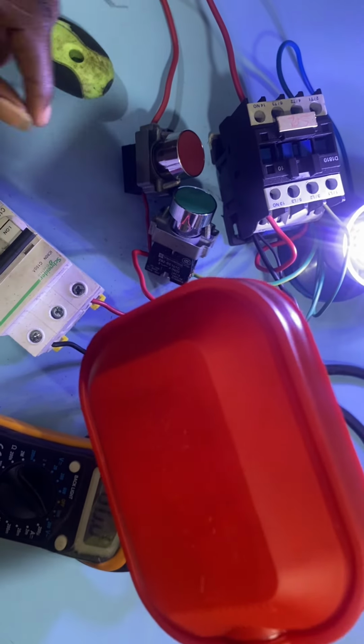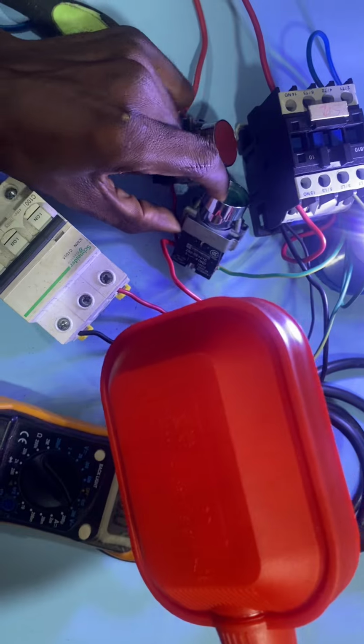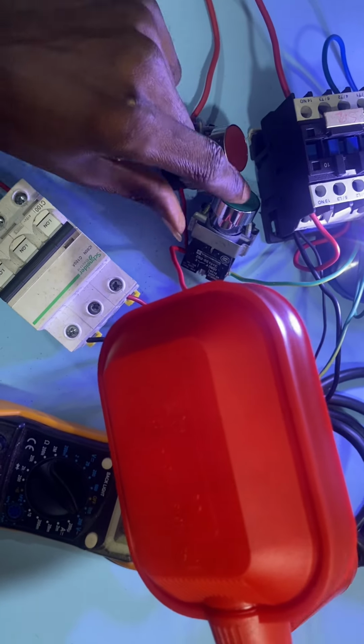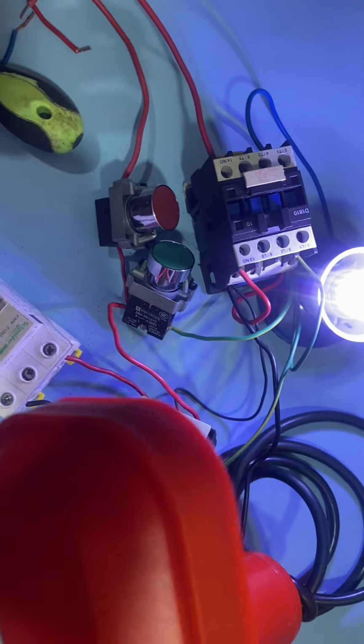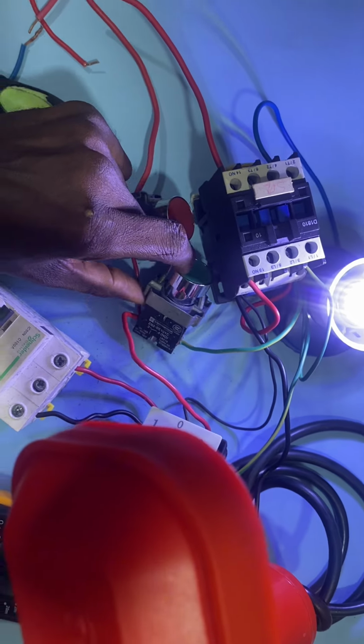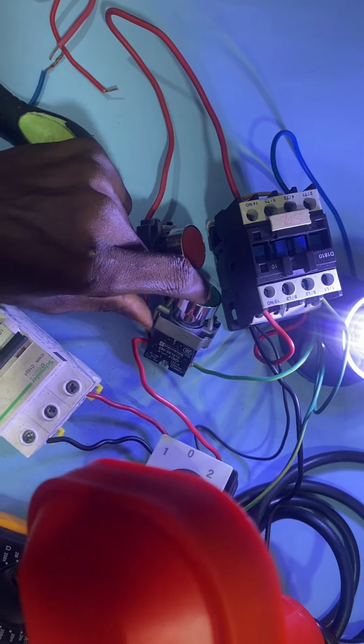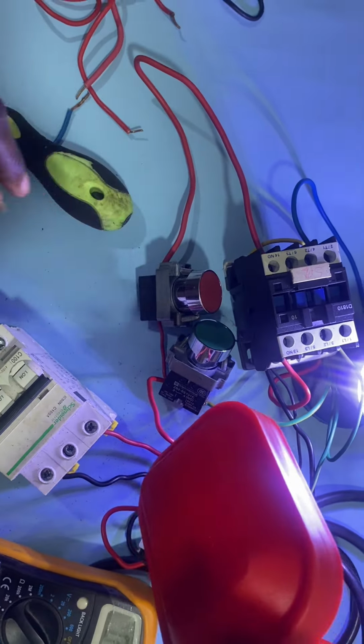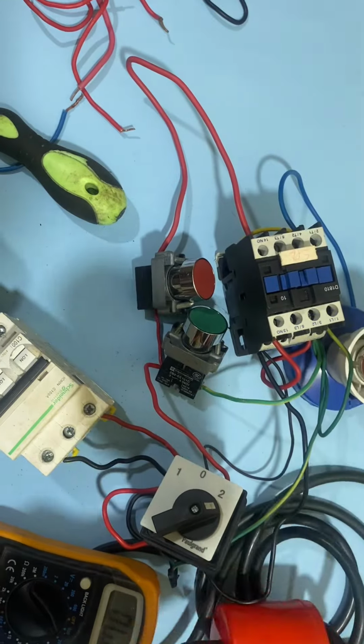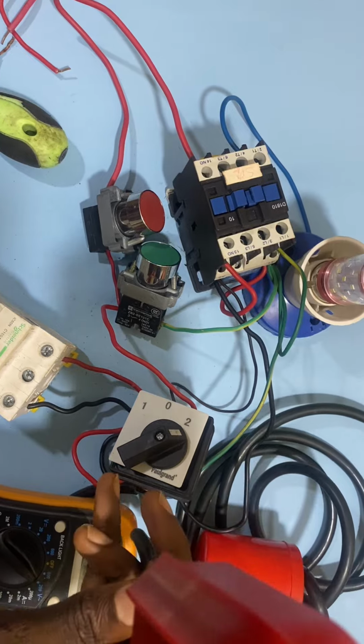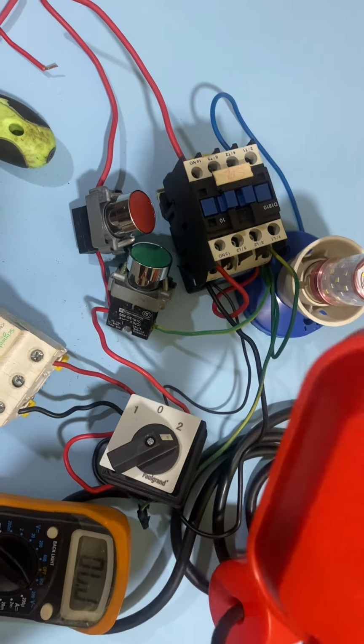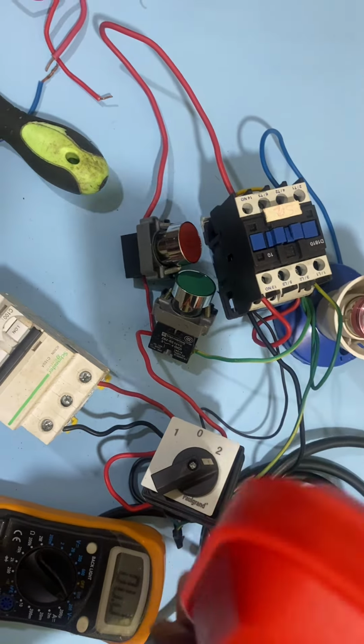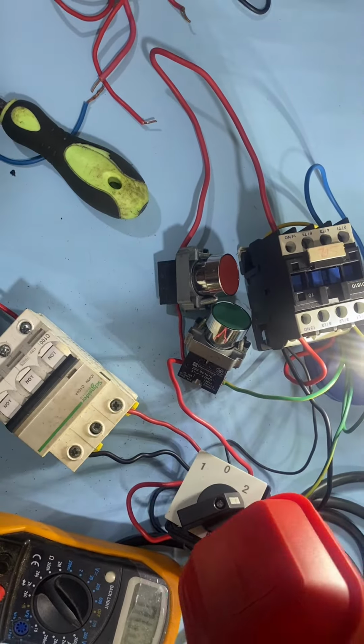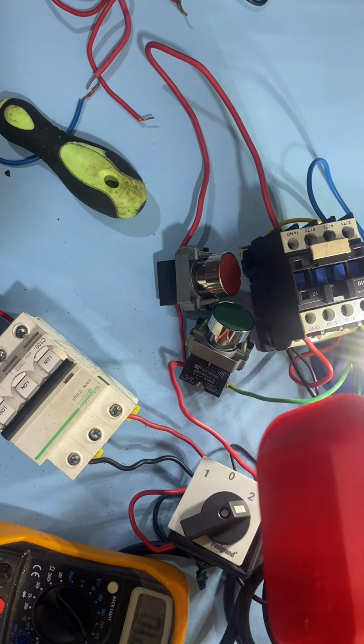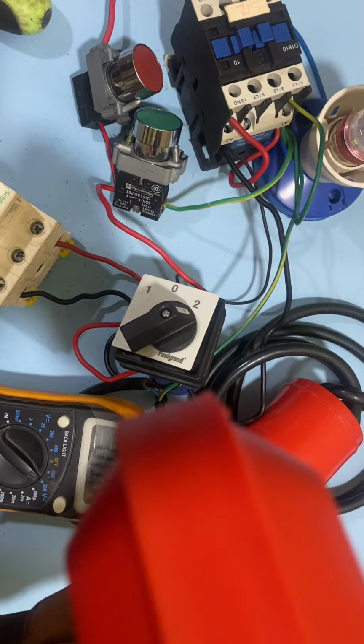At this time, you notice that when you press the start and stop button, it's not working at all. That simply means that we are not manually controlling the pumping of the water by pressing the start and stop button. Rather, we automatically control the pumping of water by using a sensor called a float switch to pump the water when there is no water in the tank, and also to stop pumping the water when water fills up the tank.